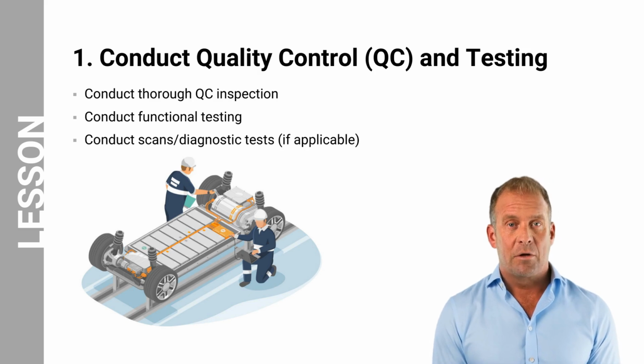Number 1, conduct quality control and testing. After completing the repair or maintenance work, thoroughly inspect the high-voltage components and the surrounding area. This quality control inspection helps identify any issues or glitches that may have occurred. Perform a visual inspection of the components, wiring, and connections to ensure everything appears in order. Look for loose fasteners, damaged insulation, or any physical damage or wear signs.